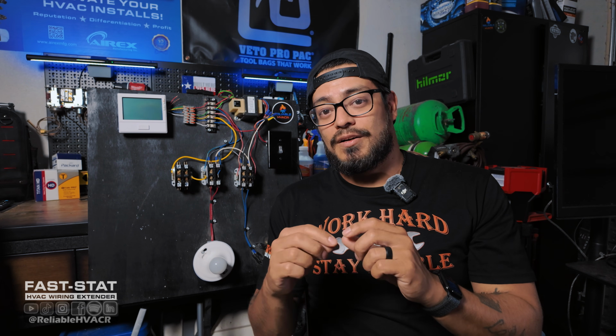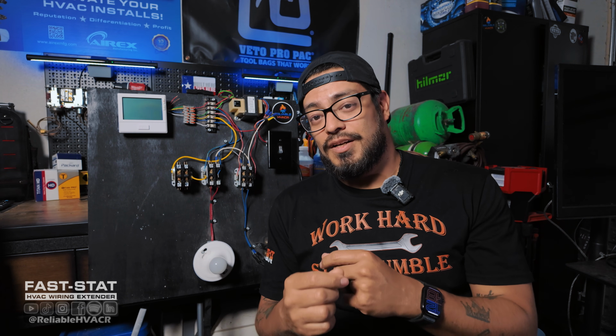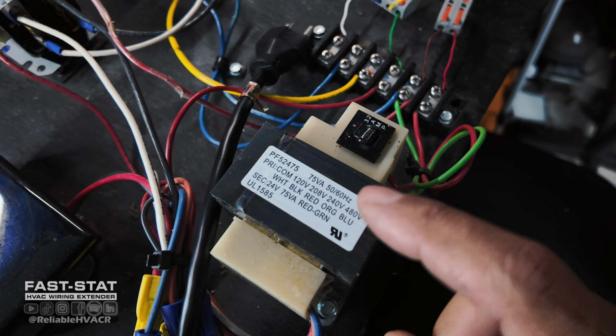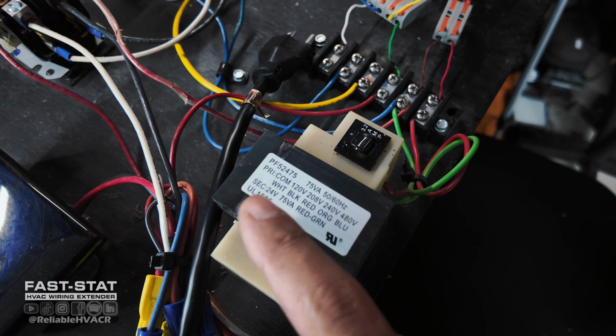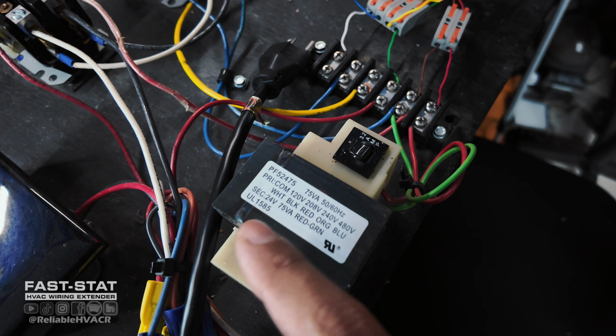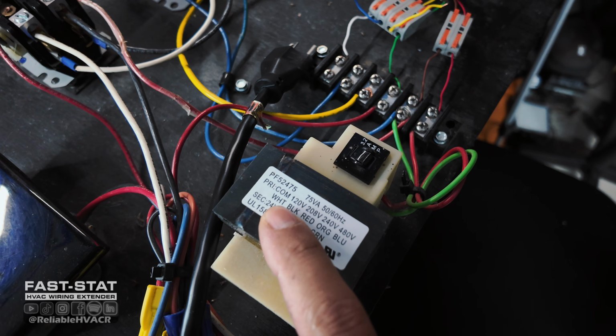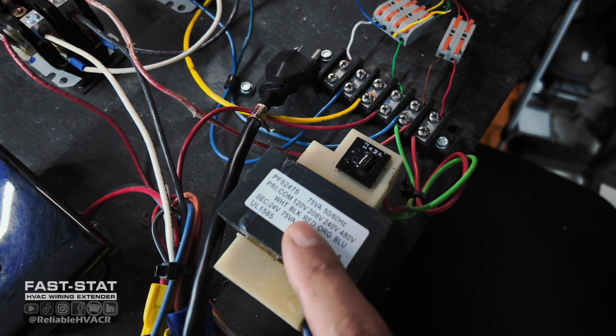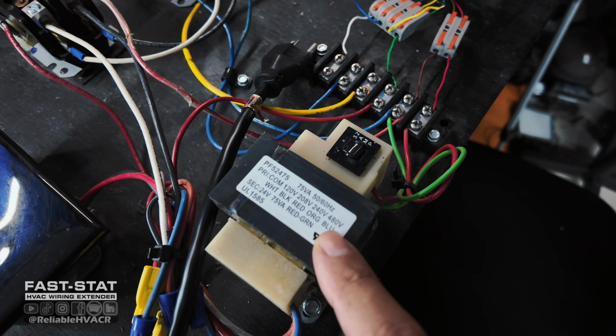If it rubs out on any bare metal or copper, you're going to get a short, and it's going to pop your fuse or the resettable fuse. One thing I almost forgot to mention is your transformer and the way it's tapped. Now I'm on commercial. This is a universal one in particular. It has 120 volt, 208 volt, 240, and 480.